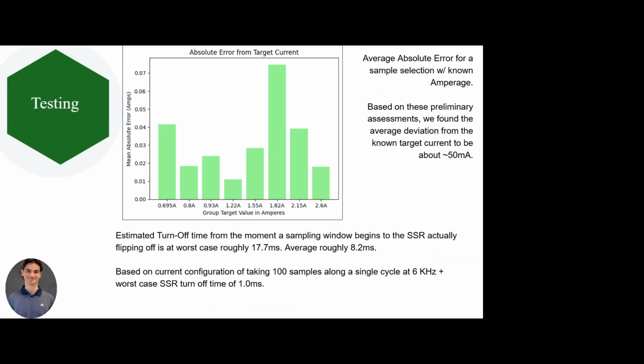In addition, we were able to calculate the worst case and roughly the average time from window sampling to when the SSR actually toggles off. And based on the current configuration of taking 100 samples at a 6 kilohertz sampling frequency along a single waveform cycle, we were able to determine that the worst case was roughly 17.7 milliseconds and averaged around 8.2 milliseconds.